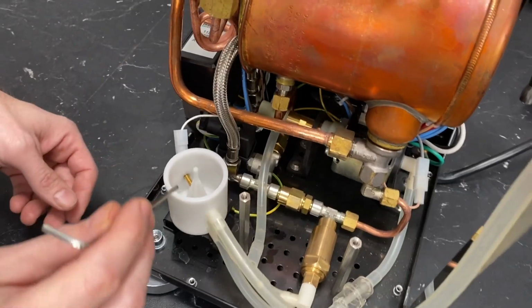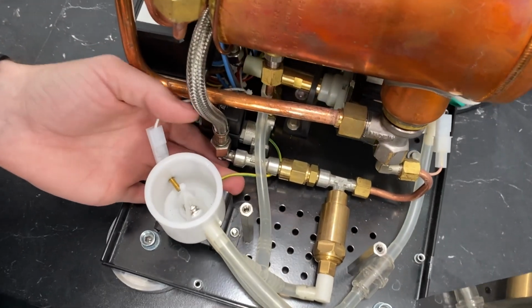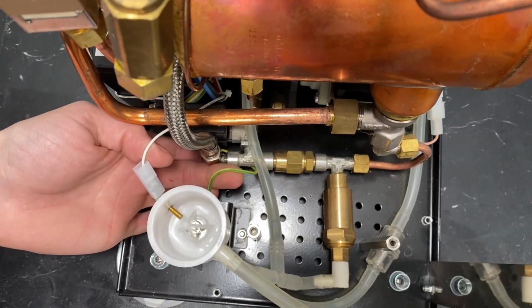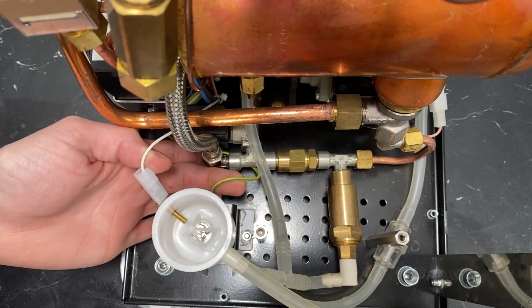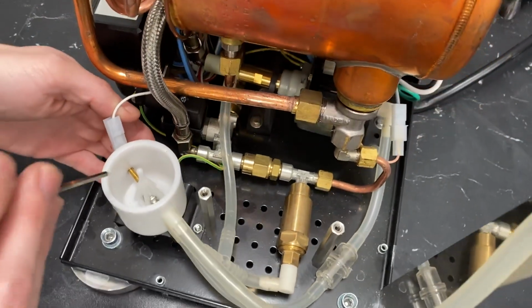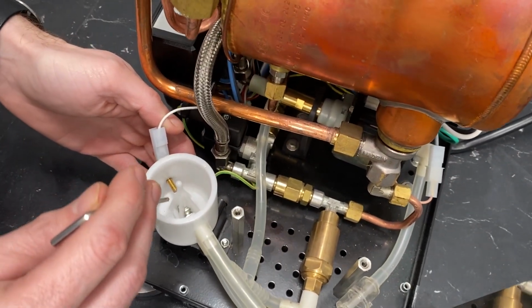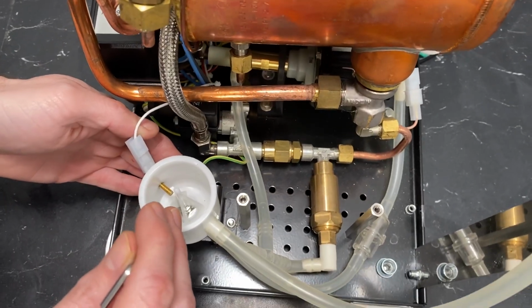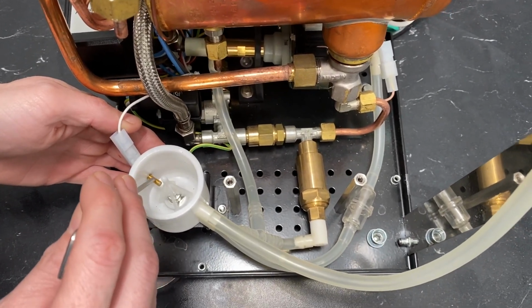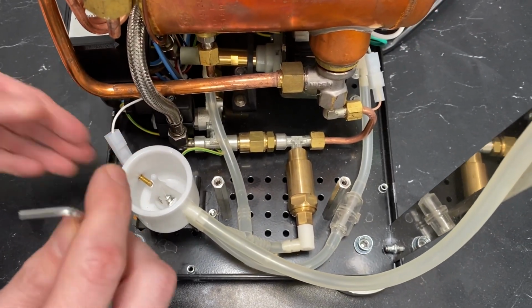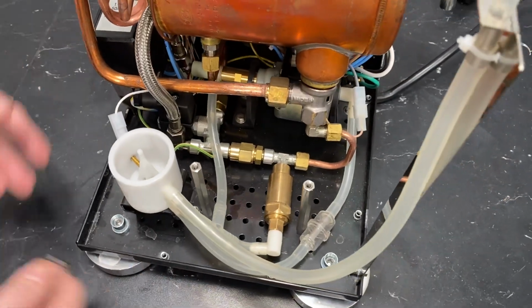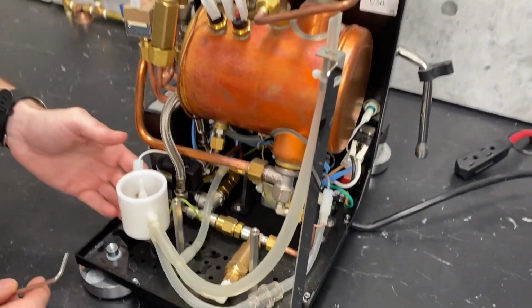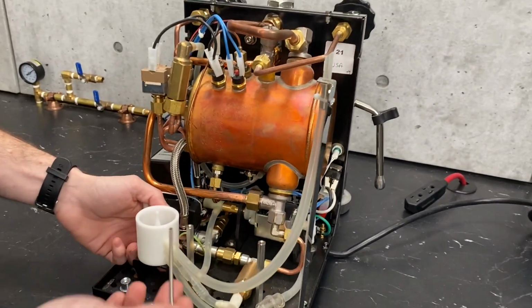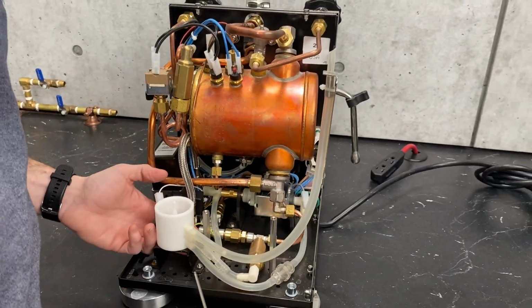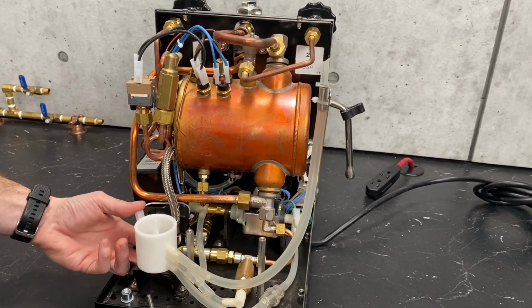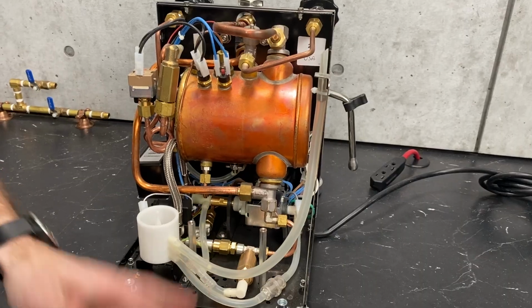On here you will see a couple wires coming off of this cup, a green striped one and a white one. This is what actually senses the water inside. The mineral content in the water conducts electricity between these 2 points, completing the circuit and saying, hey, I got water. So if you ever have an issue where your machine isn't sensing the water, check that these are all connected and everything's cleaned out, not covered in scale.